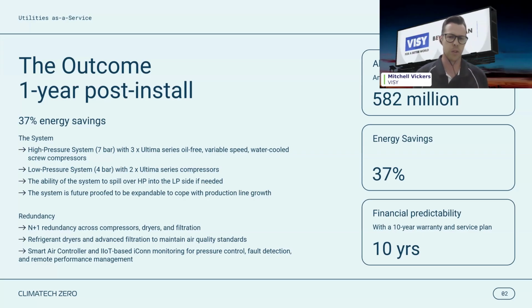And we've split the system up, so there's a high pressure and a low pressure. Through this process, we identified some components on site that could be supplied by a low pressure system, so we've got 2 dedicated compressors for that. And quite recently, we've potentially identified another piece of equipment that can be supplied directly by the low pressure, which is currently on high pressure. So that's a potential unlock moving forward 12 months in.